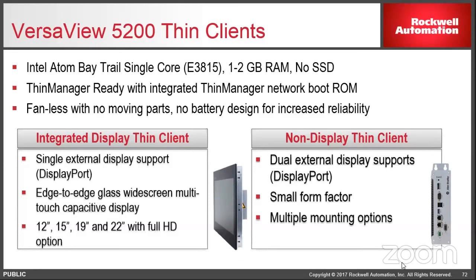And the slide looks almost identical to the PC because it's the same hardware, and it's a modular design on the inside from the factory. So we're able to go from a quad core down to a single core for the ThinManager thin client, remove some of the RAM, remove the solid state drive. So you don't need any of that stuff for ThinManager. There's no local storage here. And if there is something that happens to the system, you don't have to worry about re-imaging it. So Mike's going to get into that a good amount on the thin client side, or ThinManager side, excuse me.